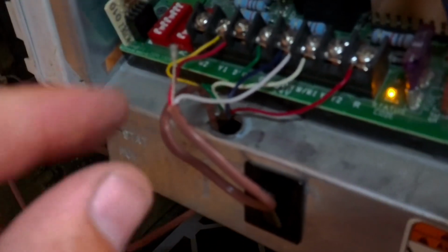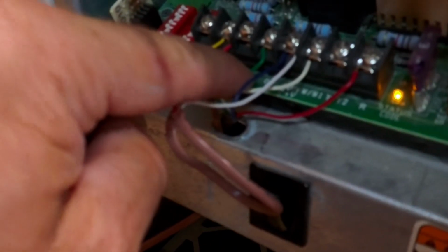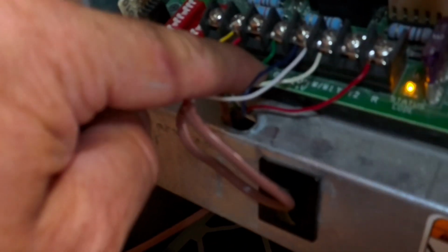When the thermostat calls for cooling, it's going to do two things. It's going to send 24 volts down the G wire, which is green if it's labeled correctly, but it's the G terminal, and that is to tell the fan in the furnace to turn on. So we need to check 24 volts from common to green and see how that is.